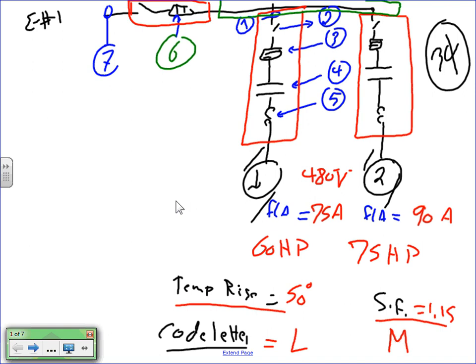They're all three-phase, obviously. They're tied through an overload, number 5, contactor, number 4, controller. Number 3 is the overcurrent protection device, a fuse. Number 2 is a disconnect. Number 1 is the branch circuit. All the way into number 6, the overcurrent protection device for the feeder, and number 7, the feeder itself. We have done that many times, and this is just a quick review.